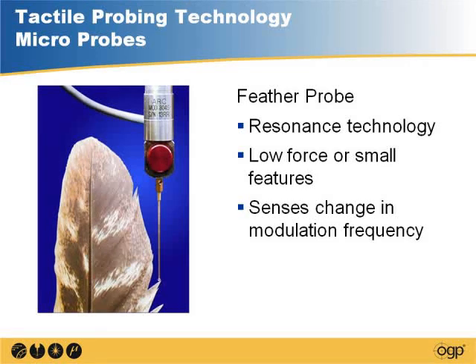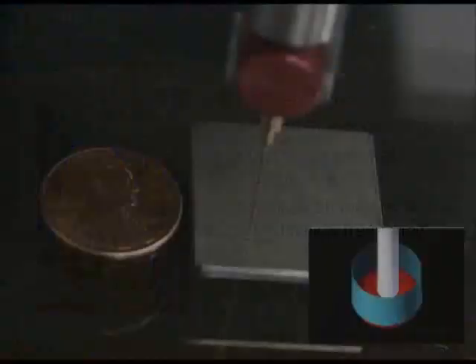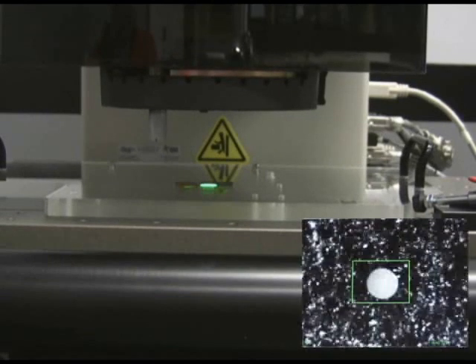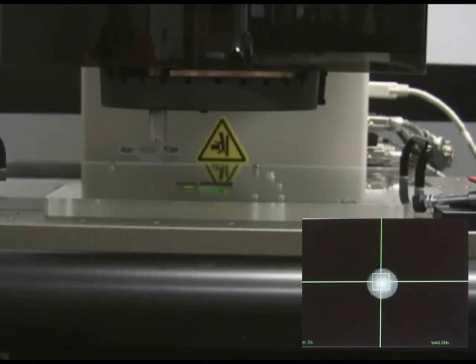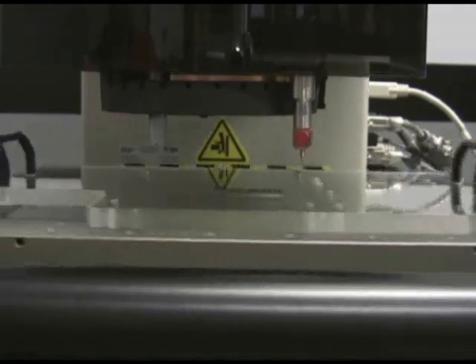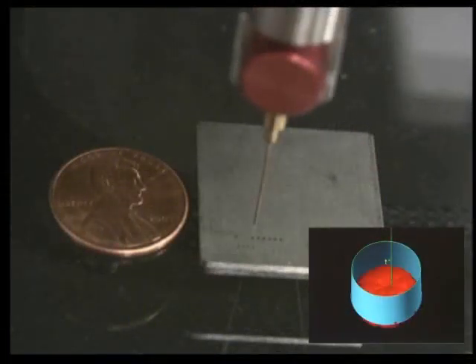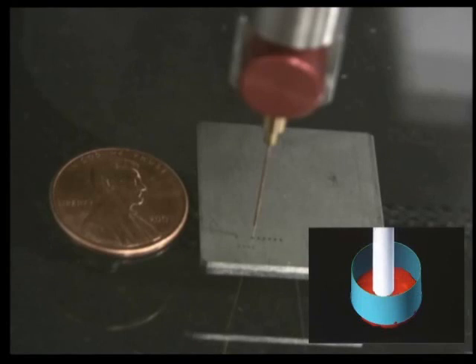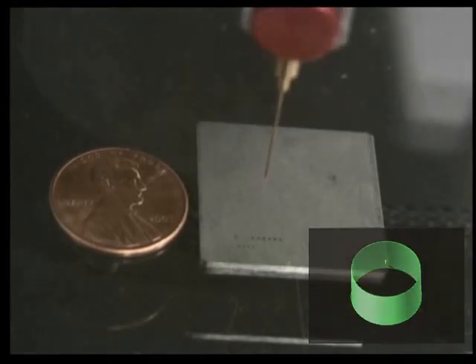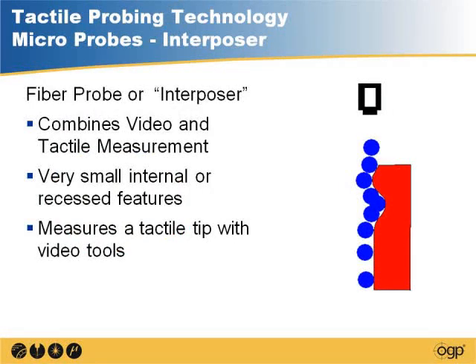So let's take a look at the feather probe. This is a very small hole. Here is an example of a small hole, with the penny there as a reference to the size. Let's take a look at this video. The advantage of a multi-sensing system is that you can measure something with video, non-contact, like it's measuring this hole here, and roughly find out where it's located, and then come in with a very small probe and know that you're going to go right down inside that hole. If the location is off a little bit, with a very small hole like that, you have the potential of hitting the probe on the surface before you go down into it. Here it's taking several points around the diameter of that very small hole. That's a 250 micron hole and a 125 micron tip was used in that demonstration.